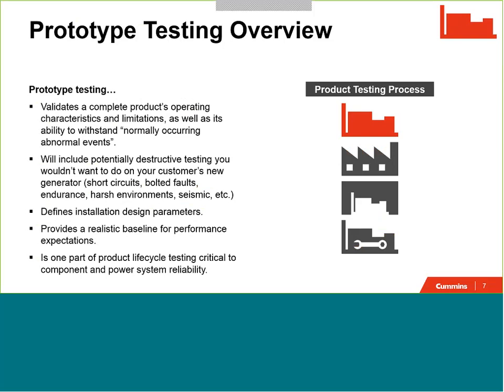And so the first point here being that prototype testing works to validate a complete product's operating characteristics and limitations as well as its ability to withstand what we refer to as normally occurring abnormal events. And what I mean by this are things that generally you wouldn't expect to see, but they do happen. These are things like a short circuit. That's obviously not something that is normal in the operation of the generator set, but certainly does happen. So this is what we would refer to as a normally occurring abnormal event.